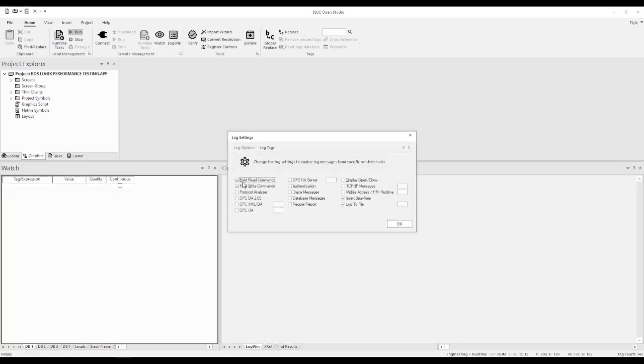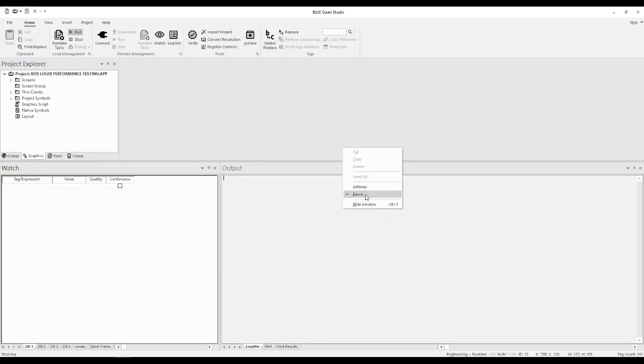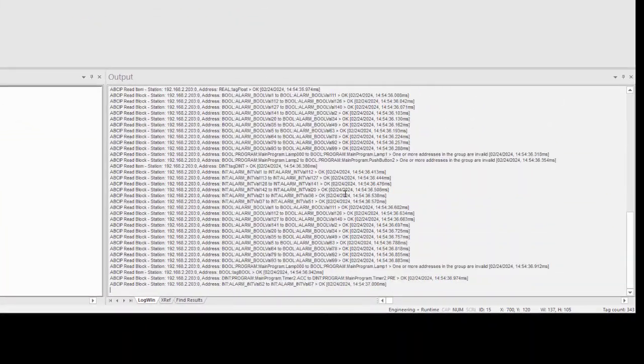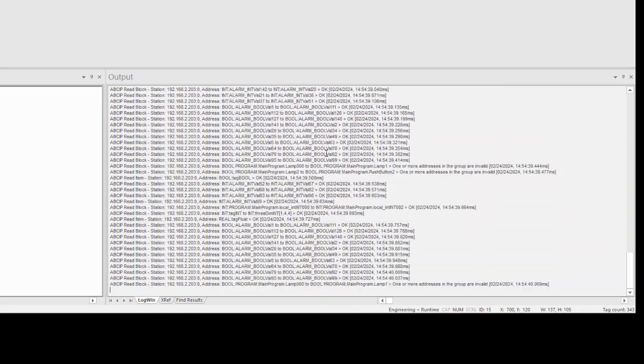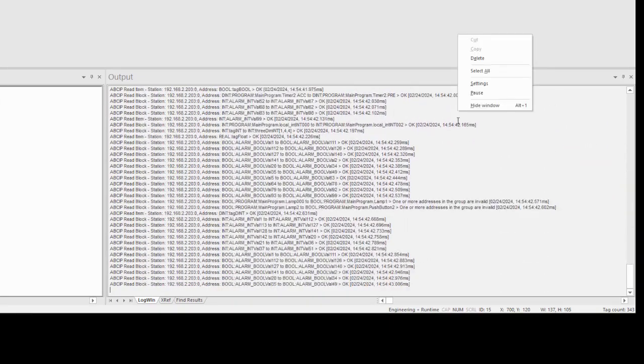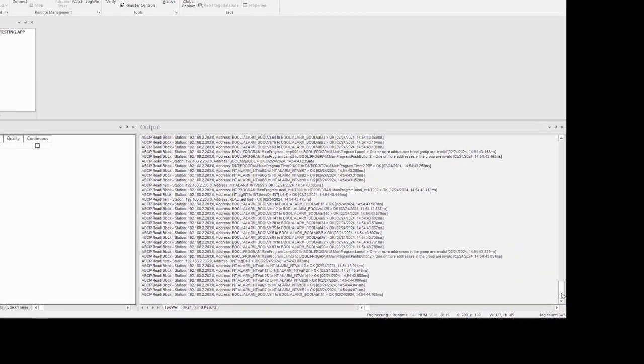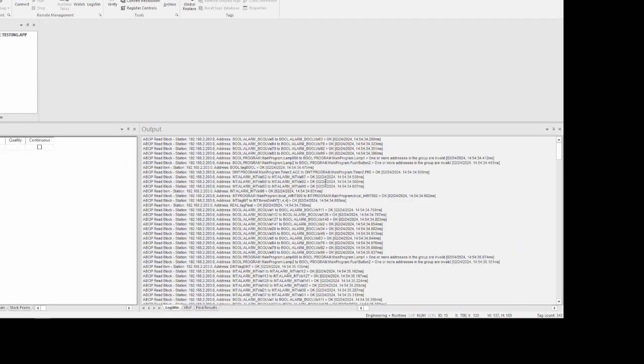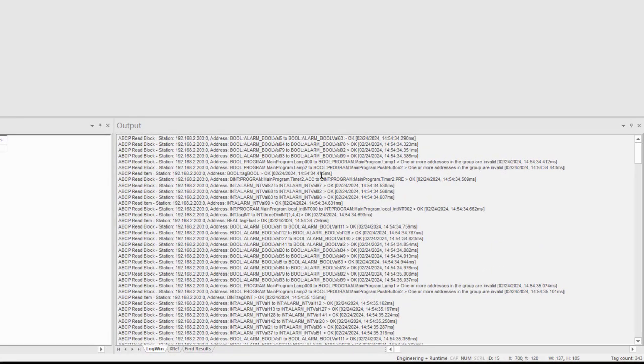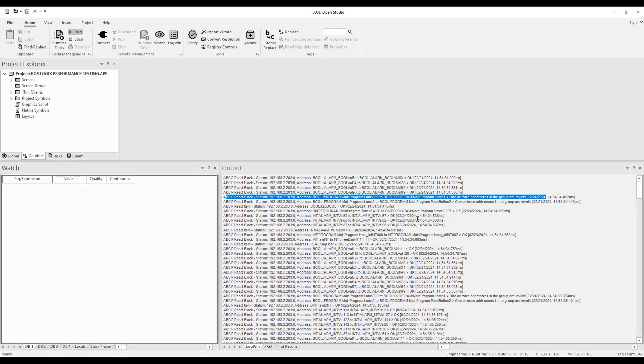Okay, so now if we go ahead and look at our watch window, like I said, all we've got is the field read and write. Let's unpause it and let it run for a little bit here. Okay, let's go ahead and pause it. And then let's find our errors. Okay, so you can kind of see we're okay. Now you can see it's right here, main program. It's basically saying one or more addresses in the group are invalid. So in the field read and write commands, you're kind of knowing that within this block there are some addresses that are invalid.